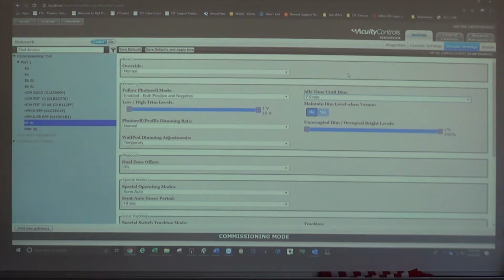So it's down to 1%? Yes, and I know that because... that's pretty dim sometimes. These dim to like 5% or 10%, depending on the building. At night you're not going to have more than 1 foot candle in the space — you'll still be able to see, that sort of thing. You can change that by adjusting the unoccupied dim level, like this.